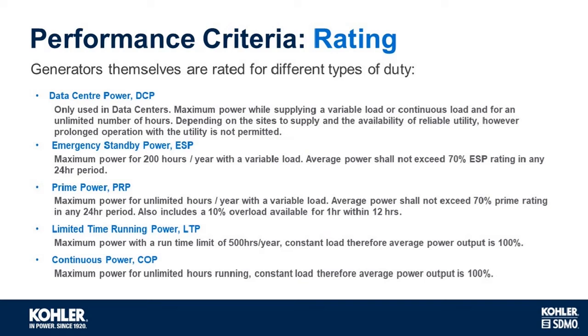It's also worth noting that some manufacturers do allow some flexibility depending on the application. Two such examples for Kohler generators are the ESP ratings are allowed to operate for 500 hours rather than the 200 hours, and the average power should not exceed 85% rather than the 70%. And likewise, we allow an average power of 75% for prime power rather than the 70%.